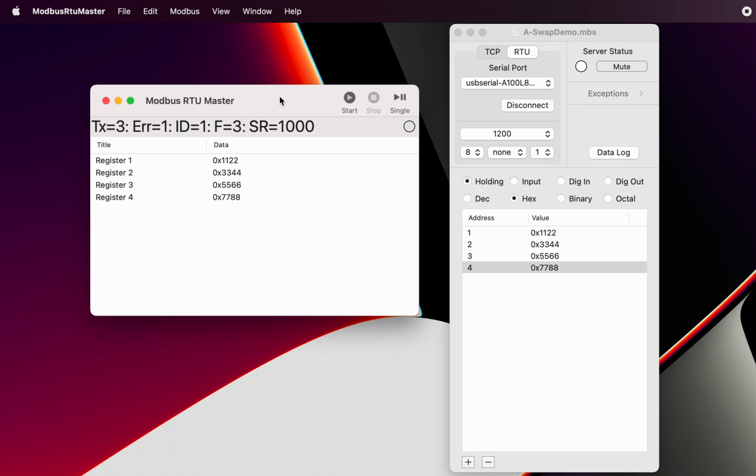The reason we're doing this is so we can see our slave. This window here is simulating our slave, and we can see in the slave we've got 4 addresses configured, and currently we're looking at those values in hexadecimal format. We've got 4 registers here. Just for a bit of information, registers are 16 bits in Modbus, so there's a total of 64 bits in here.